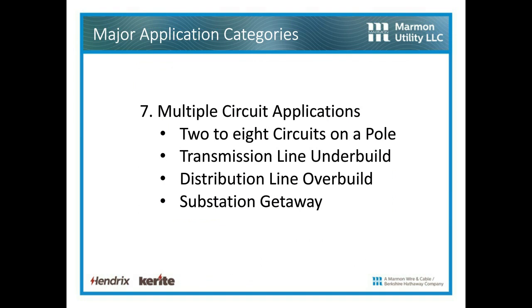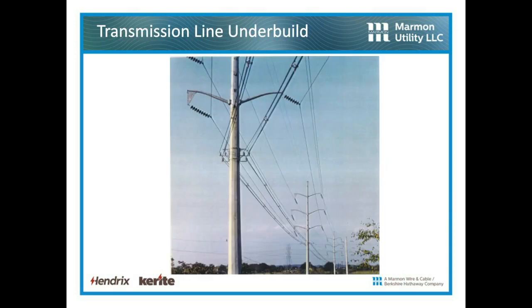Multiple circuits, there's really no limit to the number of circuits you can get on a pole, whether you're doing a transmission line underbuild, distribution line overbuild, or a substation exit. Here you can see we've got a high voltage transmission line, and it's no problem getting 2 35 kV circuits beneath the transmission structures, and it's also no problem building those long spans.